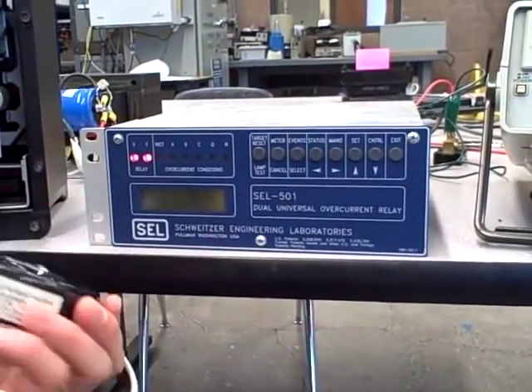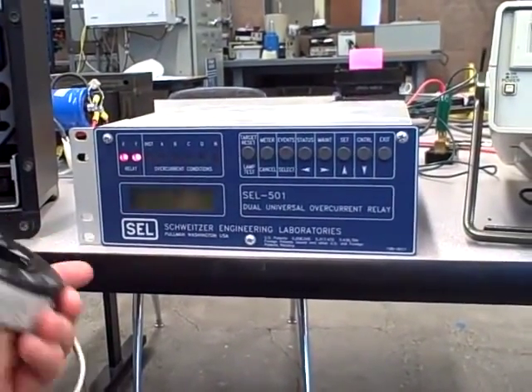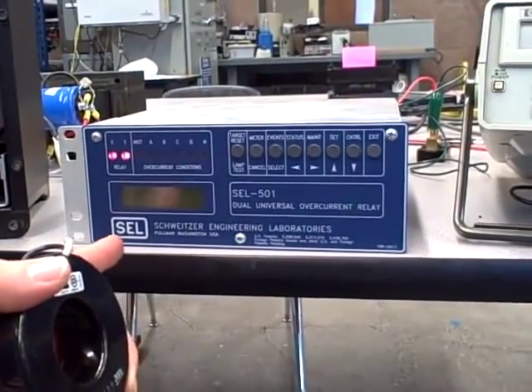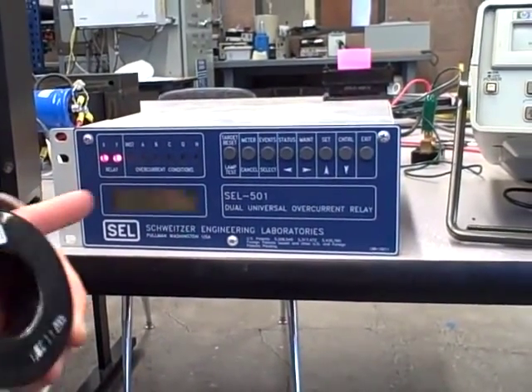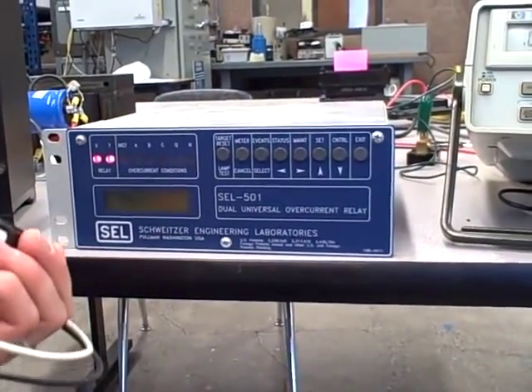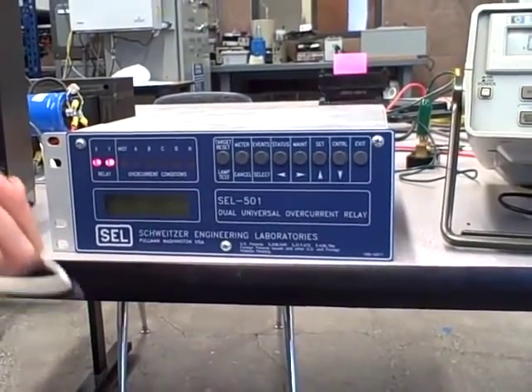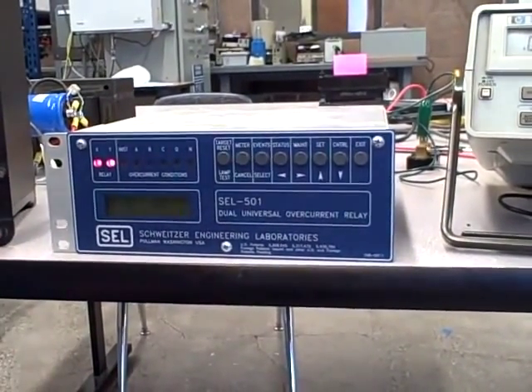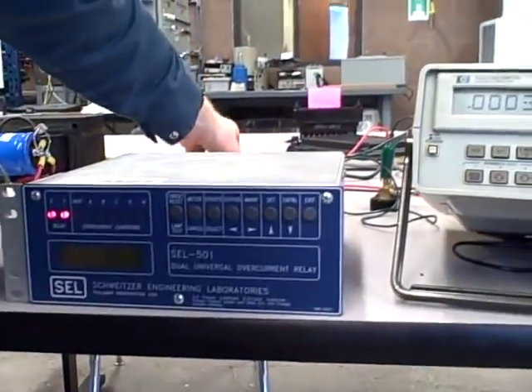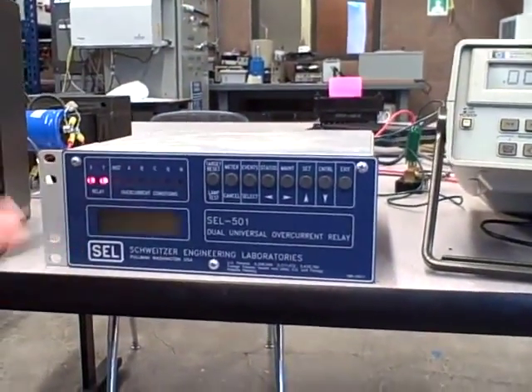Well, same thing here. We take the output of a current transformer, we run that to the digital relay instead. So instead of moving a mechanical disc, a microprocessor now times the overcurrent event and tells the breaker when to trip. Because once again, these big power circuit breakers, they need to be told by external devices like this when to trip. We're going to be monitoring that.